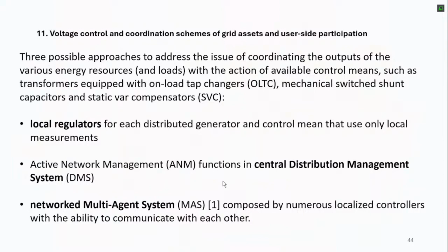We have tried to do this simulation and developed this approach. We can say at the beginning that there are three possible approaches to address the issues of coordinating the outputs of the various energy resources and loads with the action of available control means such as transformers equipped with on-load tap changer, or also capacitors and static var compensators, if they are present. And then there are local regulators. So in your PV unit, you measure the voltage at that bus and you control the reactive power of the unit based just on the voltage on that bus, so local coordination.